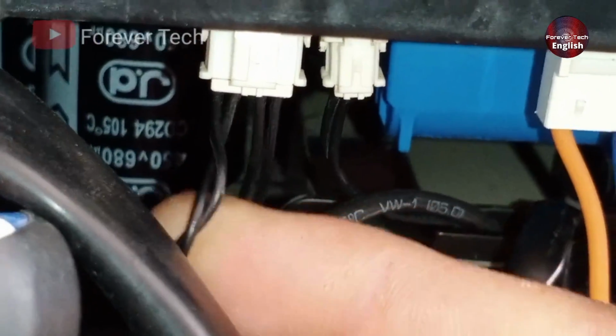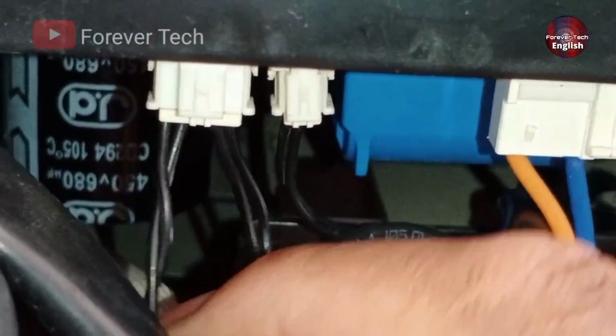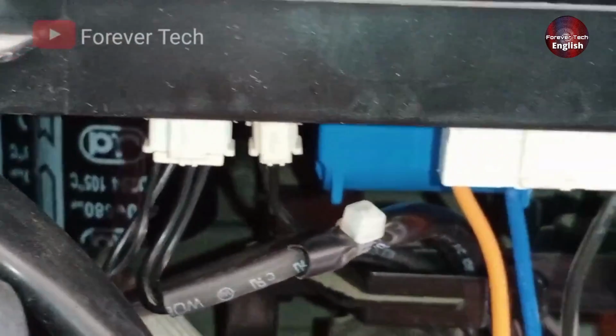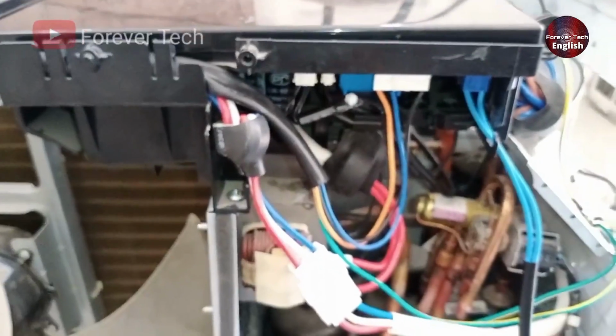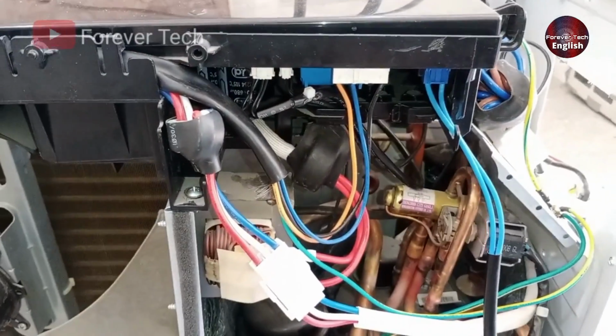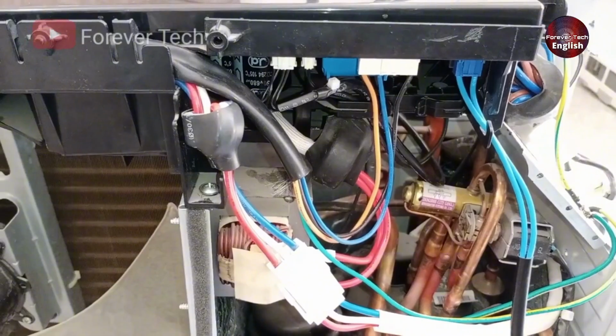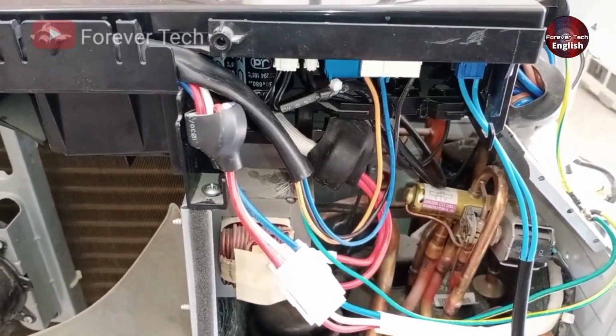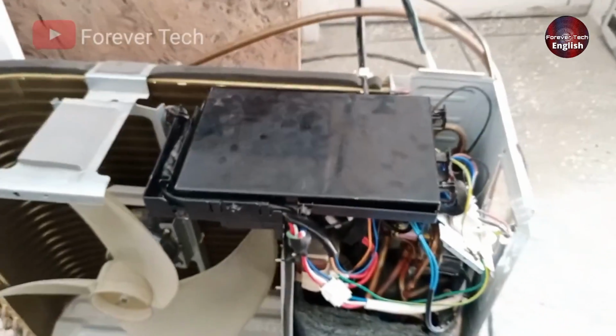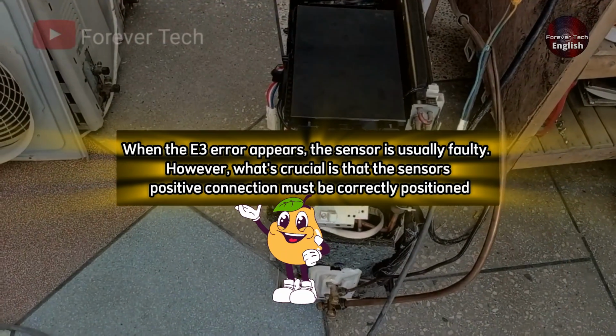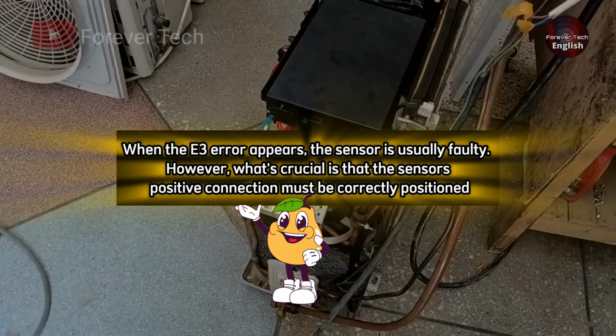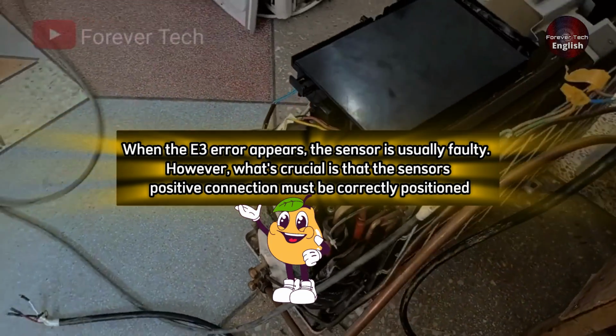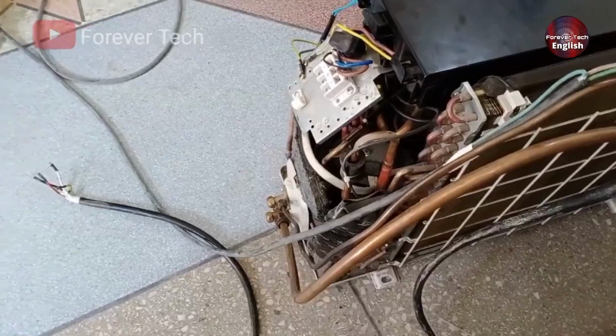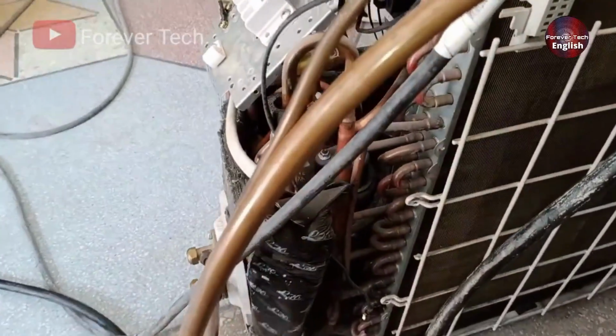If this sensor becomes faulty for any reason, it could either short circuit, its wire could get cut, the connector could come loose, or there might be an issue with the PCB. In such cases, the outdoor unit will completely stop functioning. That's why you need to replace this sensor. If the fault is in the sensor and it becomes out of order, it can cause problems. So, by replacing this sensor, your unit will be completely fixed. When the E3 error appears, the sensor is usually faulty. However, what's crucial is that the sensor's positive connection must be correctly positioned. If it's connected incorrectly, there's still a chance of errors occurring.